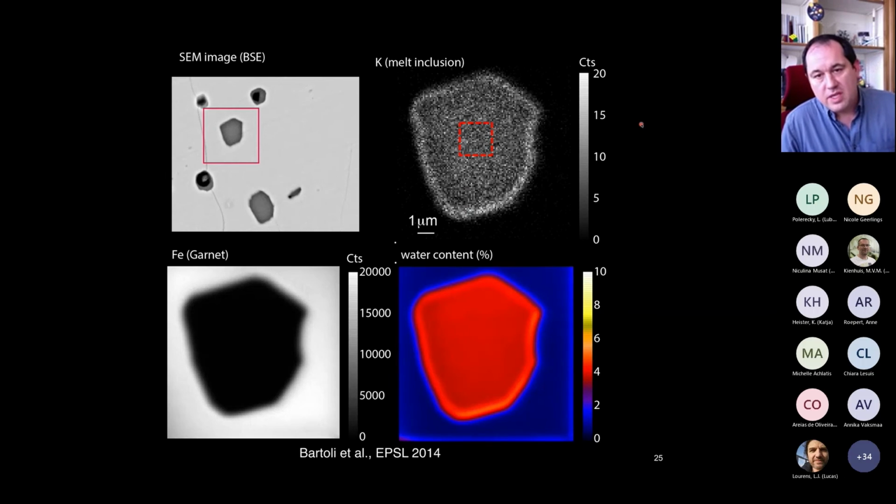Here I'm showing you a NanoSIMS image, but the way we make the measurements is not by doing images. We are using the isotope mode. So basically, we scan a square and we collect the data only from the middle of the square. The typical sampled area corresponds to this red square you have here, 1 by 1 micron, but we actually scan a larger area of about 3 by 3 microns, using the beam blanking mode to reduce the influence of surface contamination on the signal. We don't have images that we correct, we just have raw numbers that are corrected through calibration.